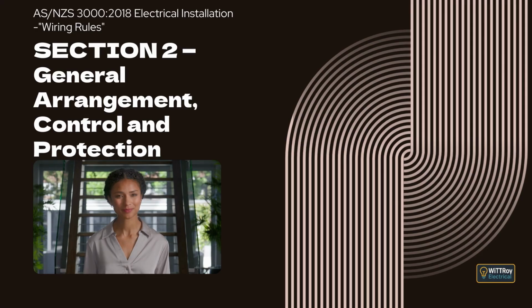Clause 2.10.2 covers the location of switchboards. Switchboards need to be placed in suitable, well-ventilated areas. They must be protected from moisture and must be arranged so that electricians can safely install, replace, or maintain equipment inside the board. That means there must be enough room in front of the board, and enough space for tools and hands to work safely. The access requirements continue with the idea that people must be able to safely reach and operate the equipment. The standard says there must be a clear space in front of the switchboard to allow safe operation and adjustment.